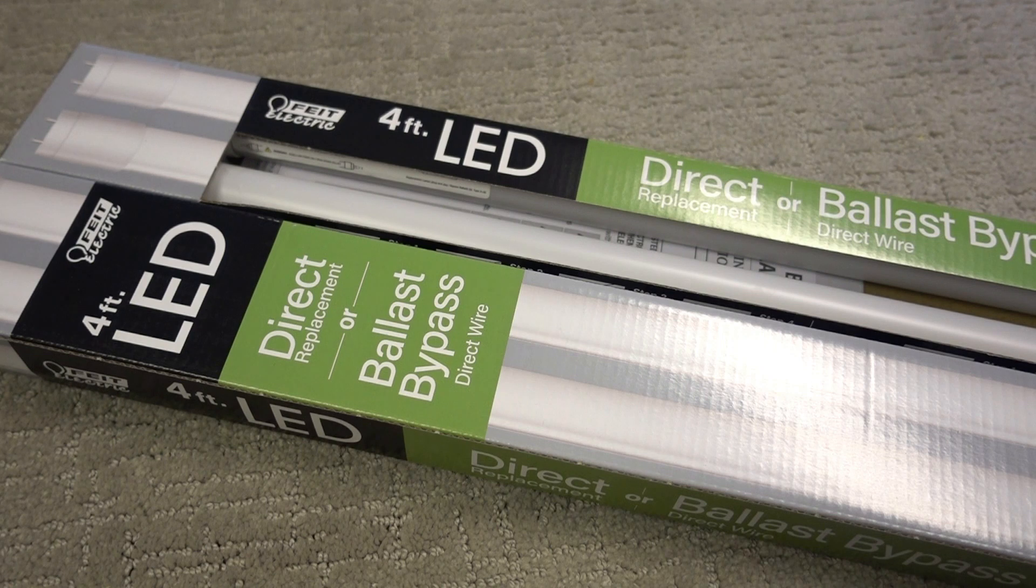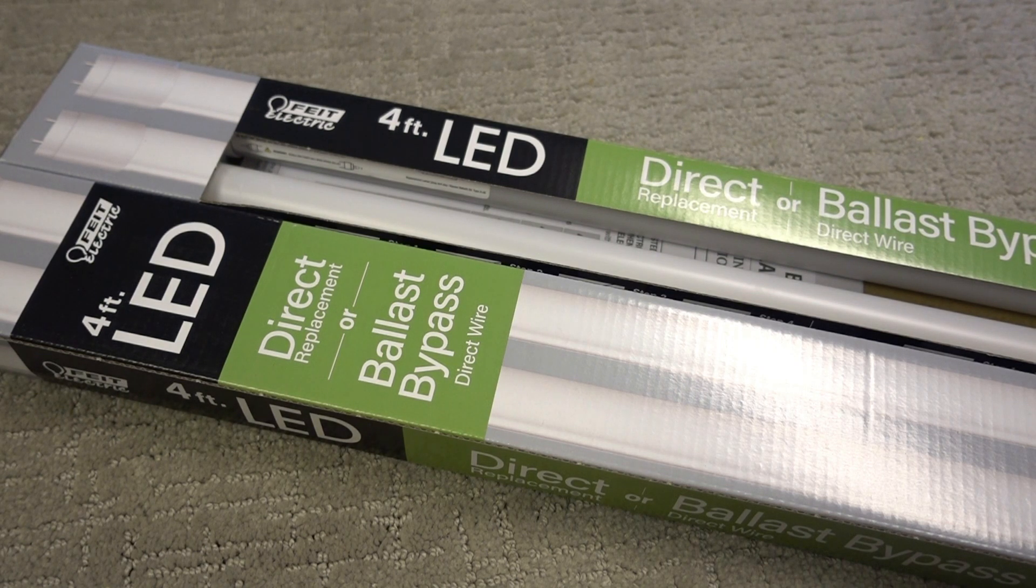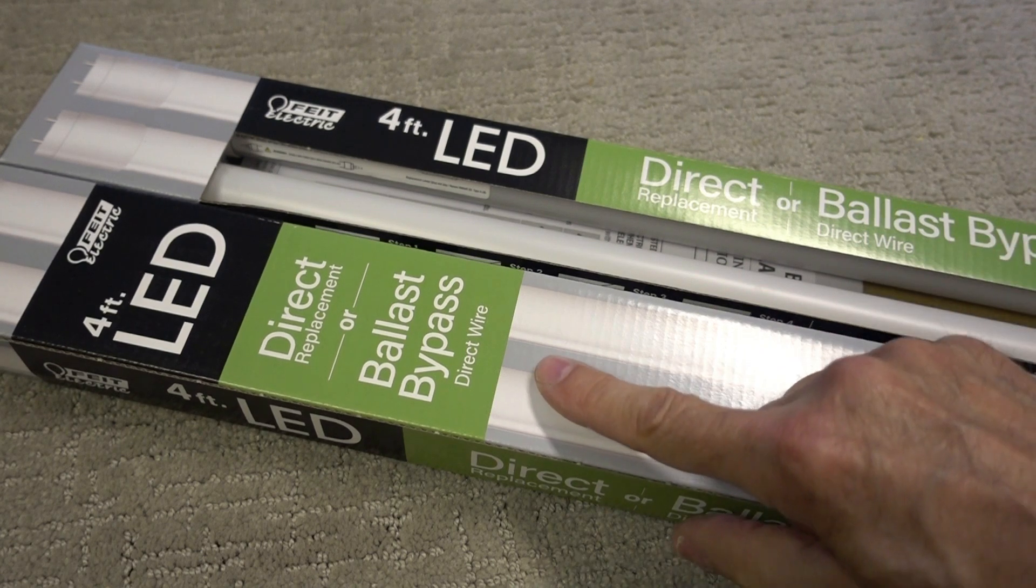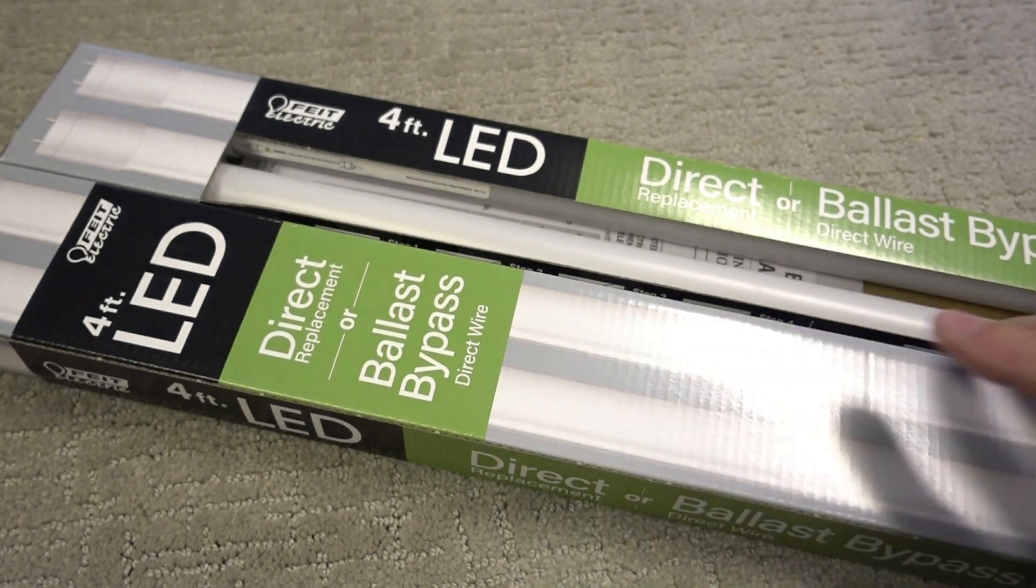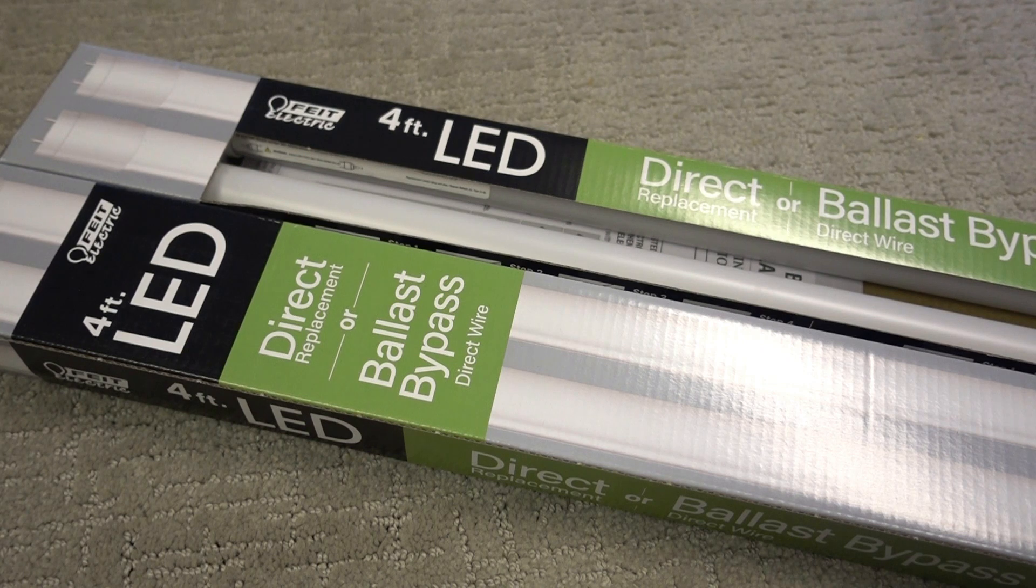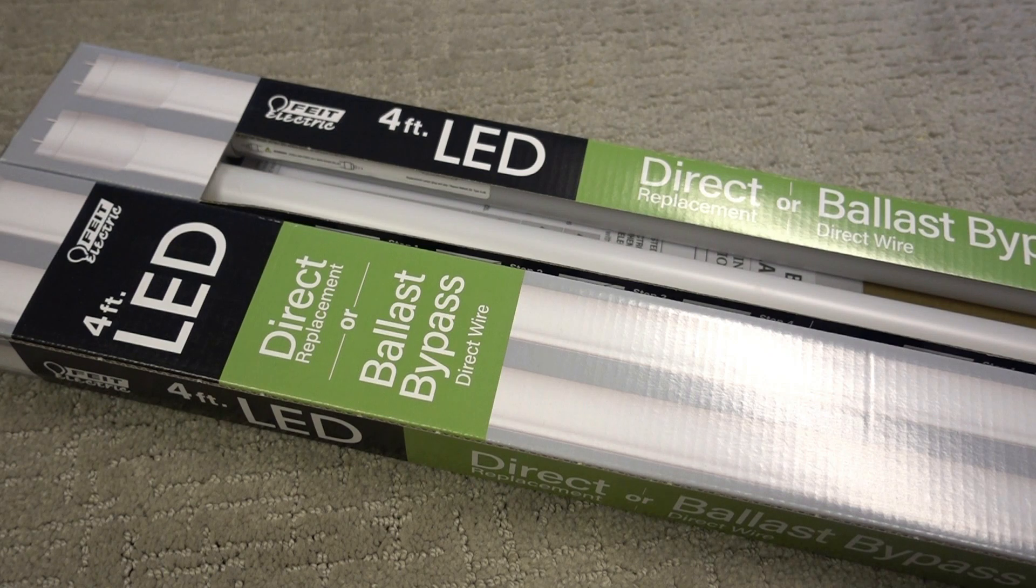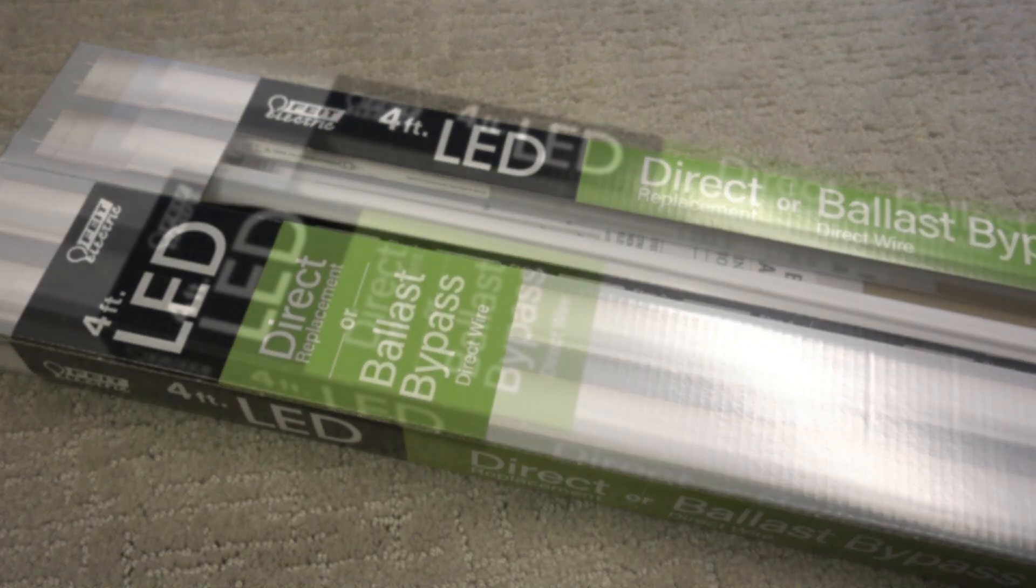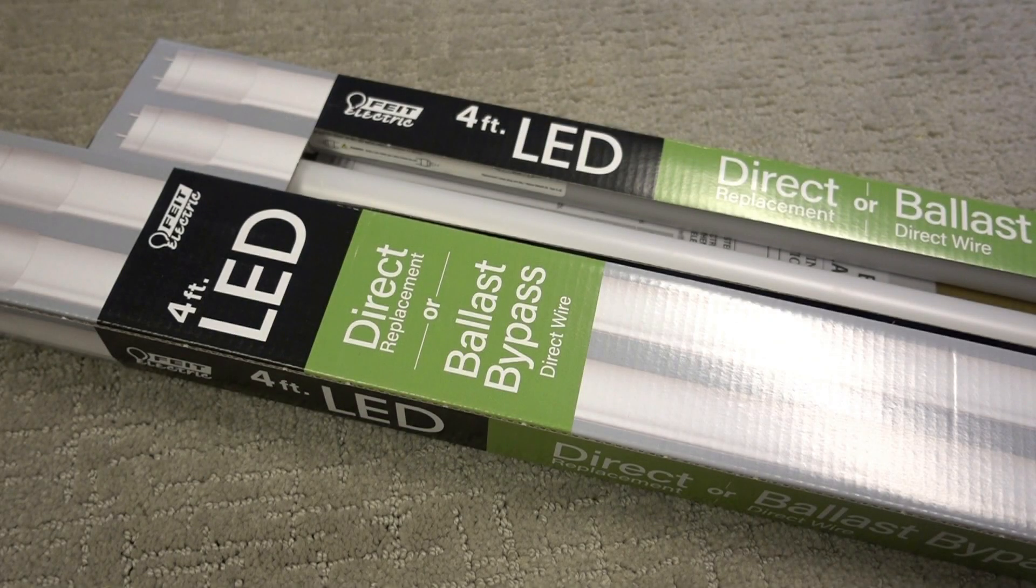What you do if the plug-and-play LEDs are not compatible with your ballast, you have to use one of these ballast bypass lamps. That involves cutting the wires to the ballast and rewiring the outlet so the power goes directly to the outlets in the fixture. When you see the term direct replacement, that is the same as saying plug-and-play.